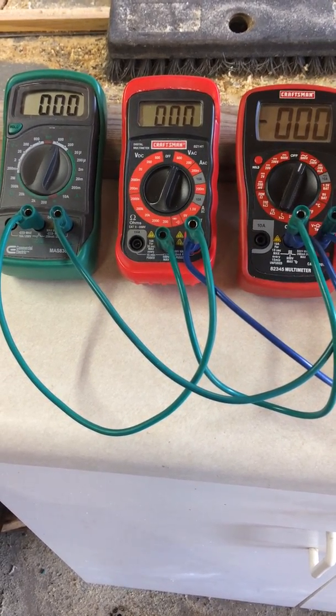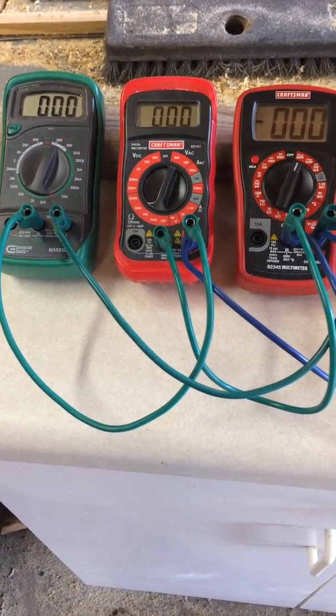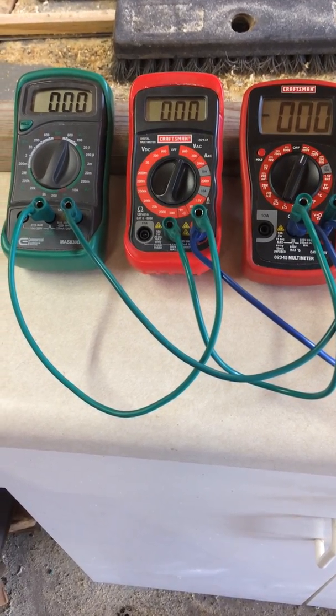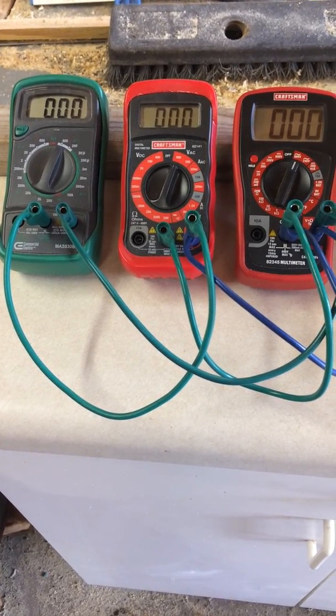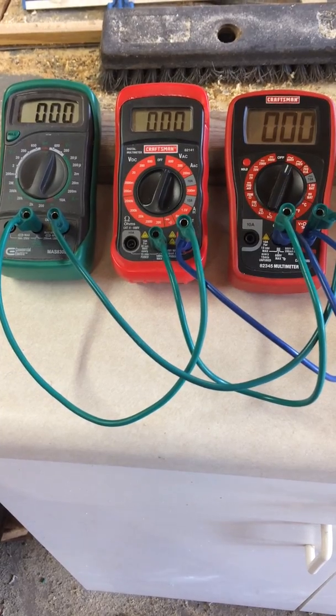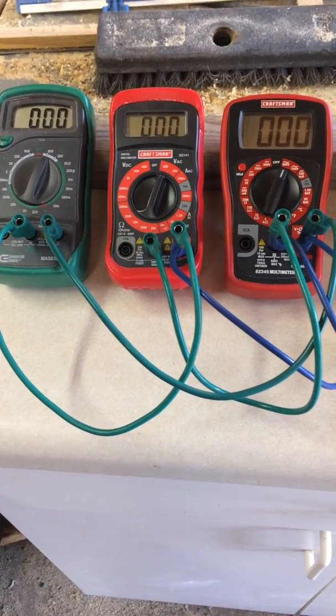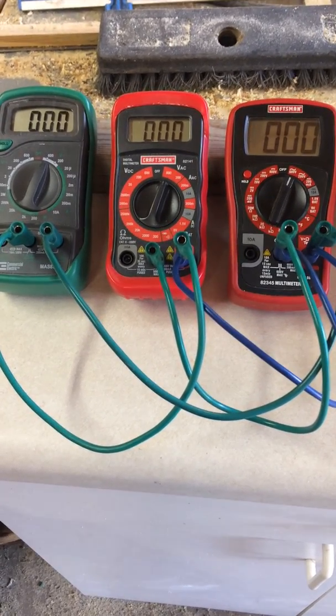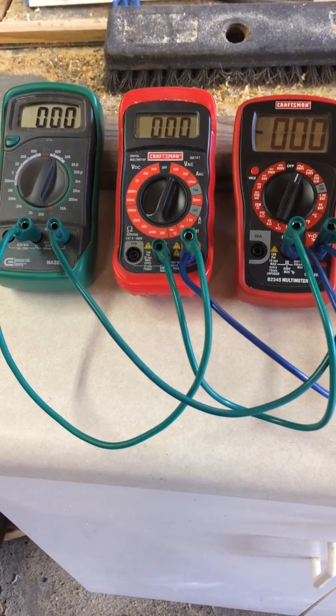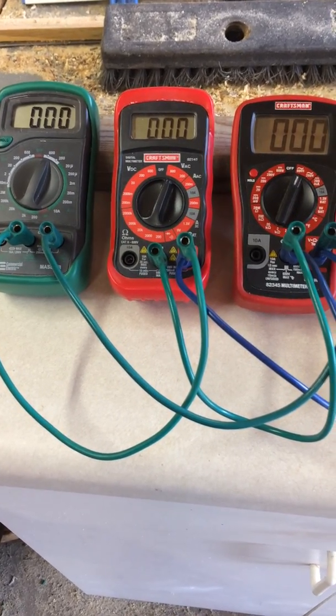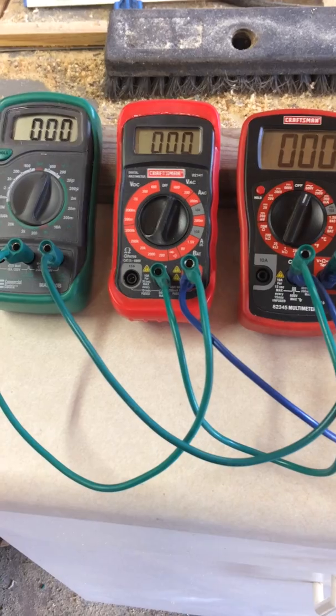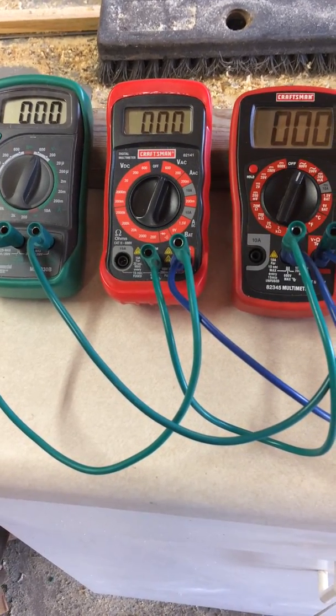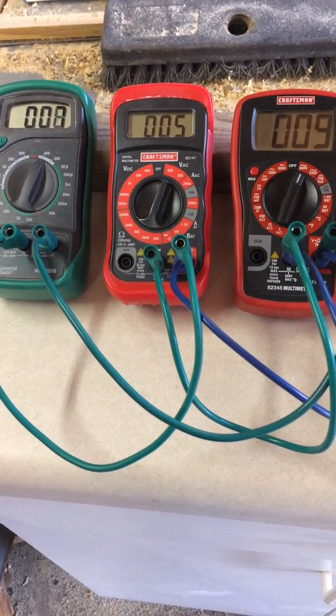And we get into an odd situation if one of the primary overcurrent devices would open up. And in the case of a pad mount transformer, the thing will actually start to howl and sound like it's going to come right off the ground. I can't quite do that with this setup, but I'm going to show you the basic mechanism of it. So I'm going to start to increase my voltage from the power supply.